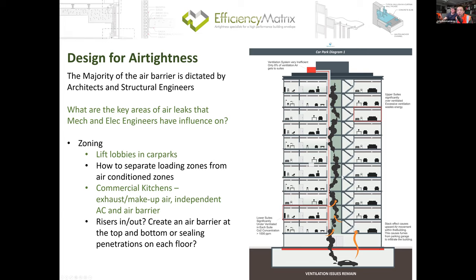So if you make those decisions early on, especially if you try to cap off the riser, you need to somehow coordinate the ductwork and the cable tray so they have a flat surface or end at the same level. You can easily put a flashing on to seal it off, instead of trying to slot in a piece of sheet metal here and a piece of sheet metal there and try to seal it, which is virtually never going to work if you try to do it as an afterthought.